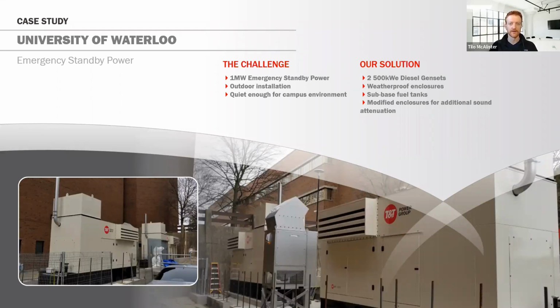This is a typical problem we have to solve for standby power. This is the University of Waterloo in Ontario, close to where I live in Kitchener, with a 1 megawatt emergency load. It's an outdoor installation on a campus, and through that wall behind the generator is a lecture hall. So when these come on during an emergency, or for routine testing, they have to be quite a bit quieter than you might require in an industrial area or remote location where sound levels aren't a problem.